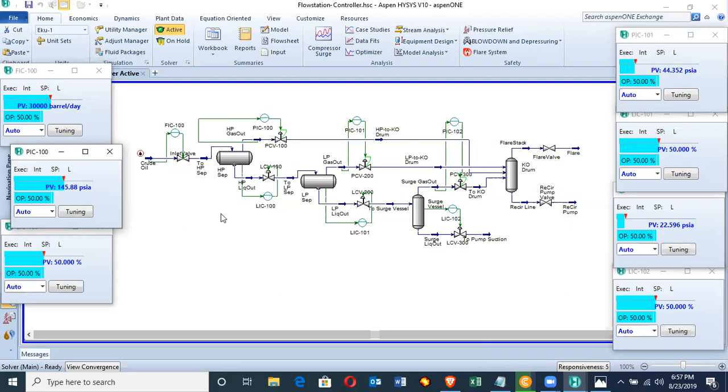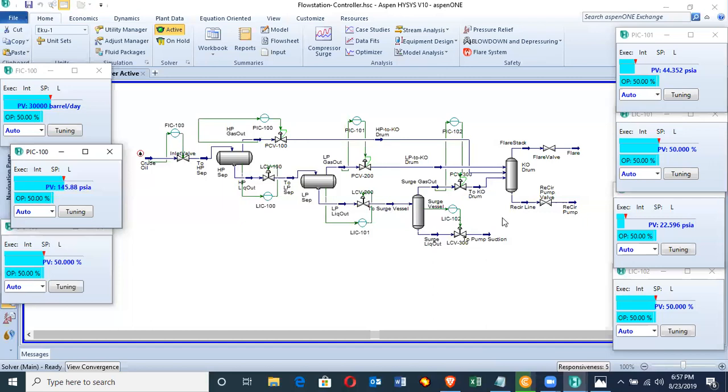Now, before you can carry out the dynamic simulation, you must ensure that your steady-state modeling is very accurate and all equipment in your model are sized appropriately. The valves should be sized, all vessels should be sized, and if you have a pump or a compressor, those equipment need to be sized before you can run a dynamic simulation.